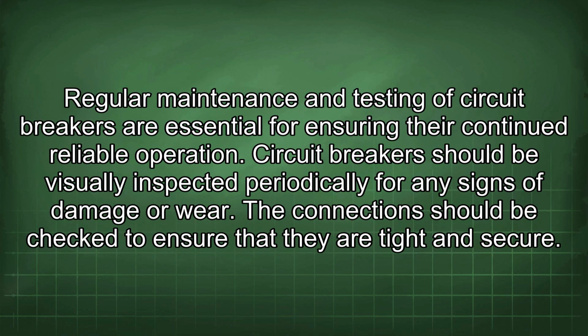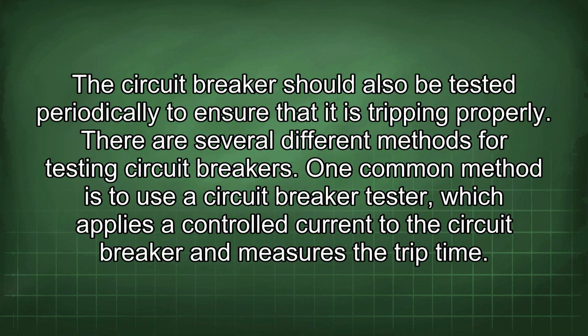Regular maintenance and testing of circuit breakers are essential for ensuring their continued reliable operation. Circuit breakers should be visually inspected periodically for any signs of damage or wear. The connections should be checked to ensure that they are tight and secure. The circuit breaker should also be tested periodically to ensure that it is tripping properly.